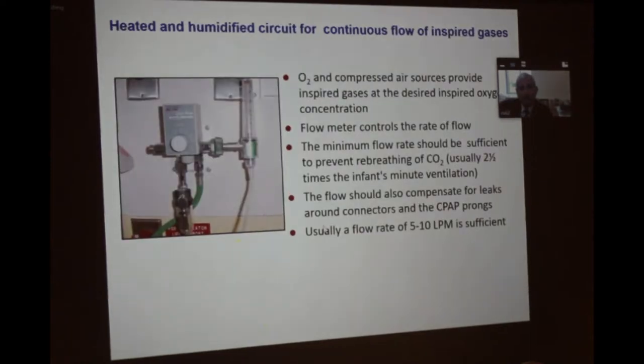Some salient features of the setup: oxygen and compressed air sources provide inspired gases at the desired inspired oxygen concentration, and the flow meter controls the rate of flow. The minimum flow rate should be sufficient to prevent rebreathing of CO2, usually 2.5 times the infant's minute ventilation. The flow should also compensate for leaks around the connector and CPAP prong, and usually a flow rate of 5 to 10 liters per minute is sufficient.